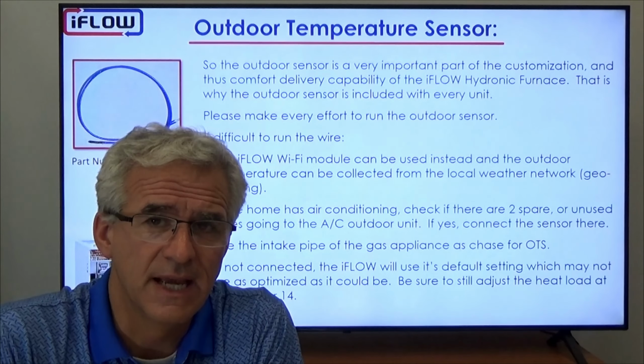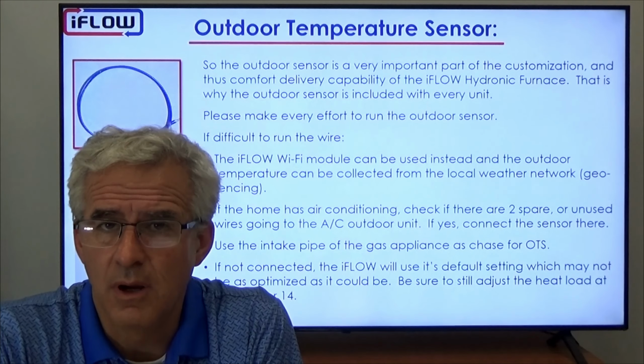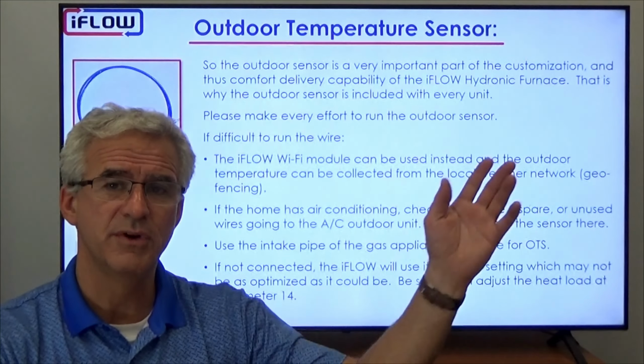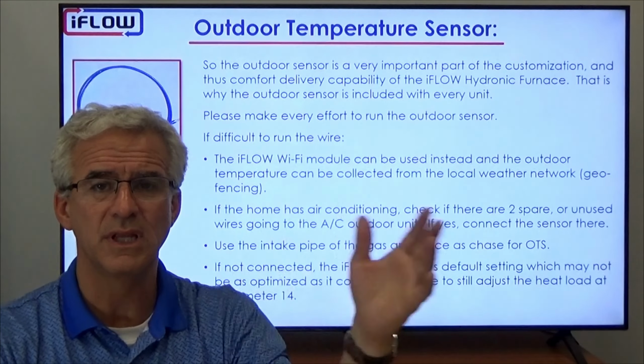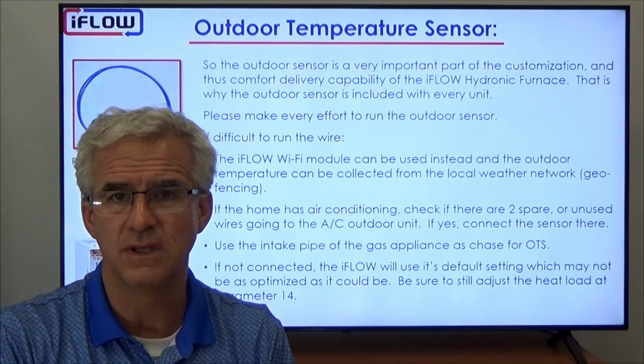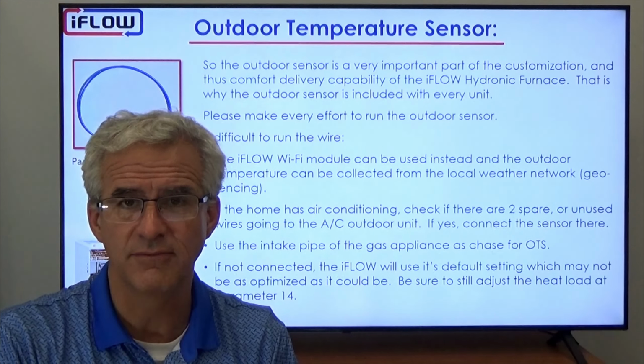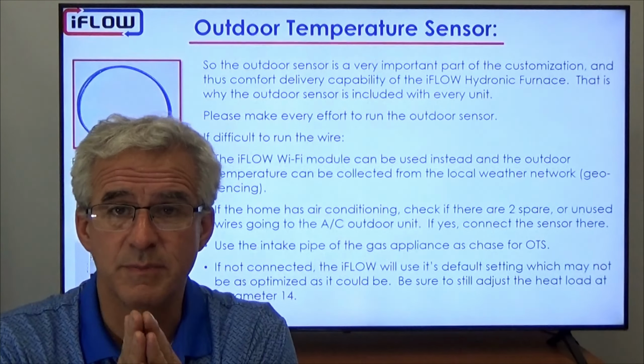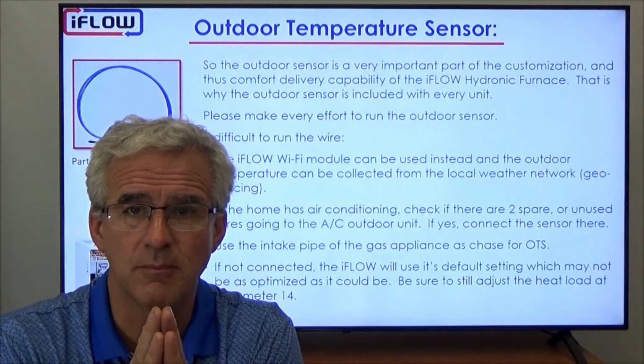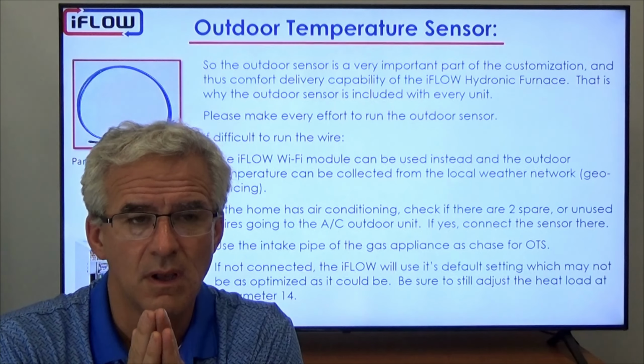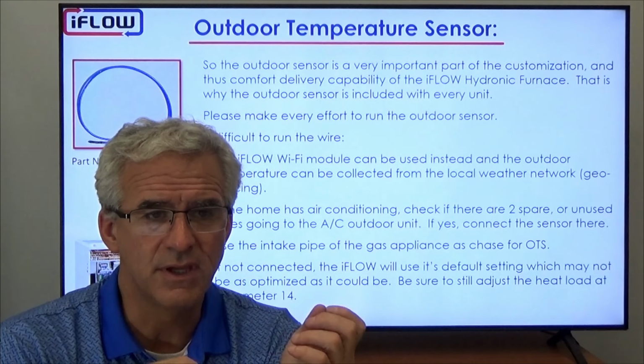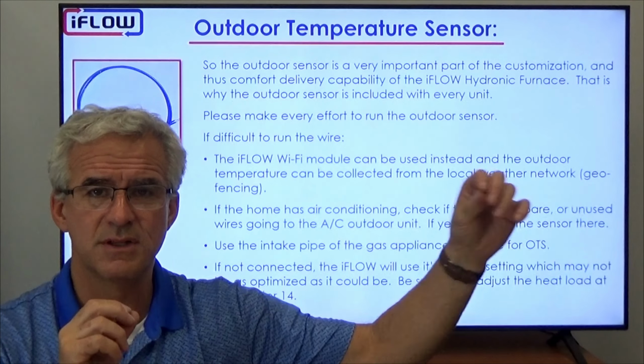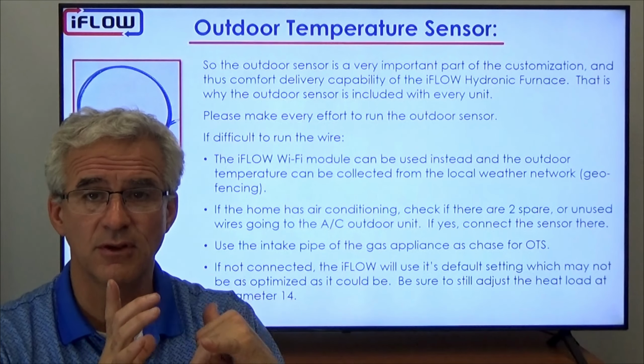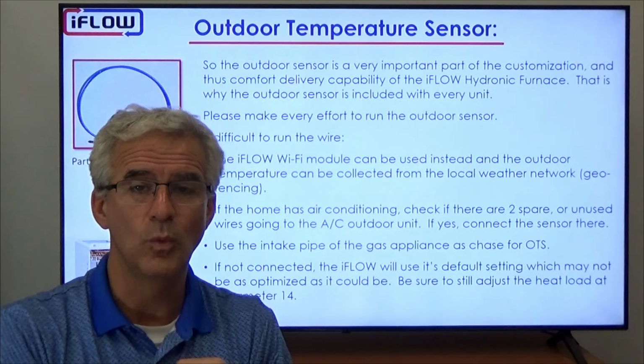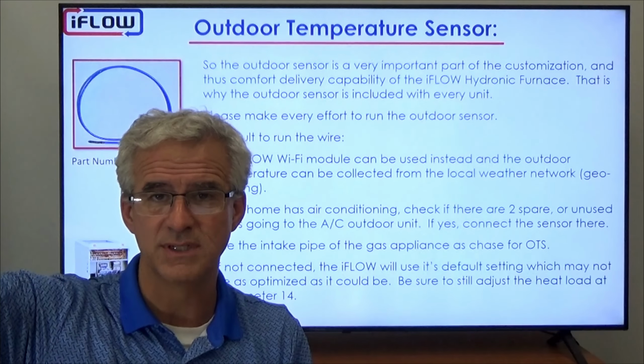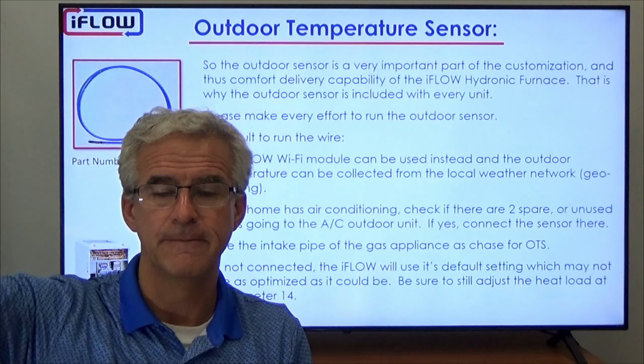Another question I often get is, okay, I'm running with a combi boiler. I've got the outdoor reset on the combi boiler. Do I really need it set on the iFLOW? And the answer is yes, because both need to be doing the same thing. So with a Navien, the outdoor sensor is connected to the iFLOW. The iFLOW, based on the slope we set, will then tell the Navien what temperature to run at, which is great.